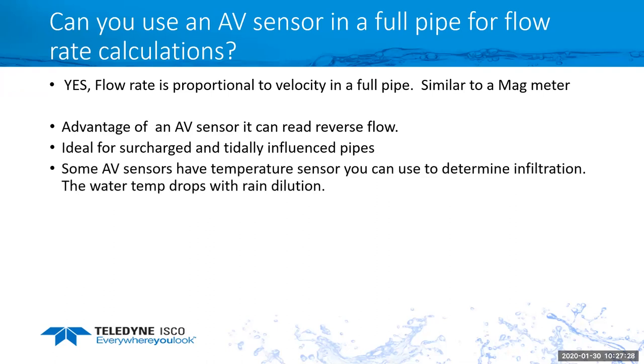Some AV sensors, area velocity sensors, have temperature sensors built in. What's nice about that, and I recommend that you log the temperature, is that if you're doing an I&I study and your flow rates change and you see that the temperature starts to drop, that's an indication that you're getting rainfall in your pipe, because you're going to see the temperature drop as your flow rates are changing due to rainfall coming in.